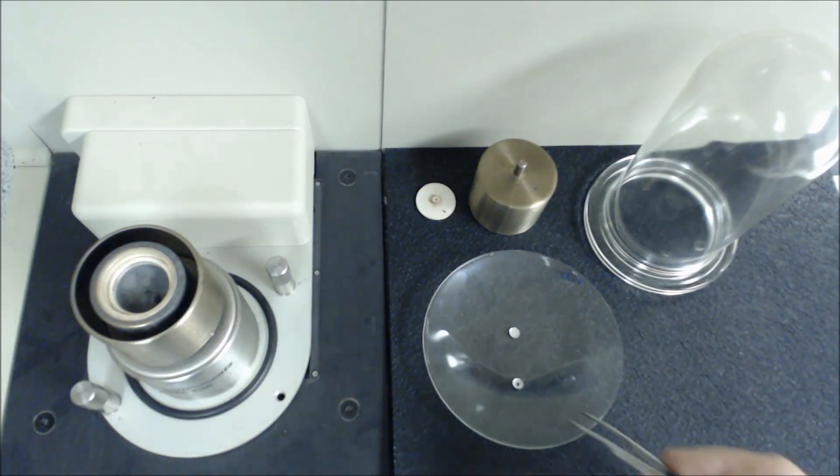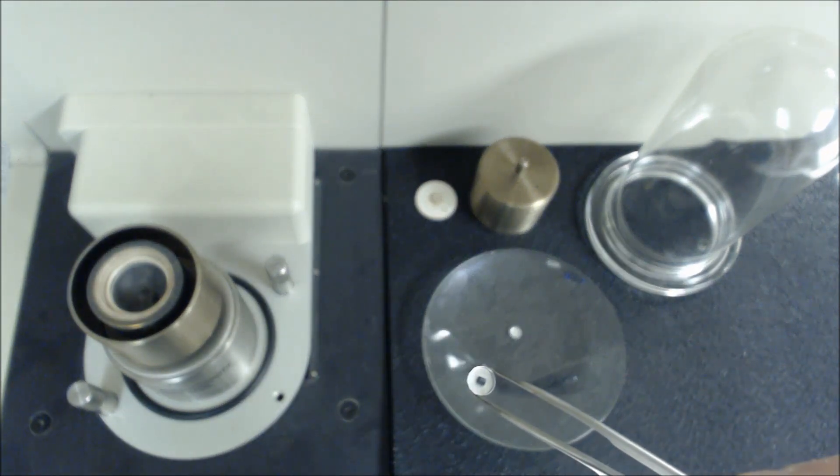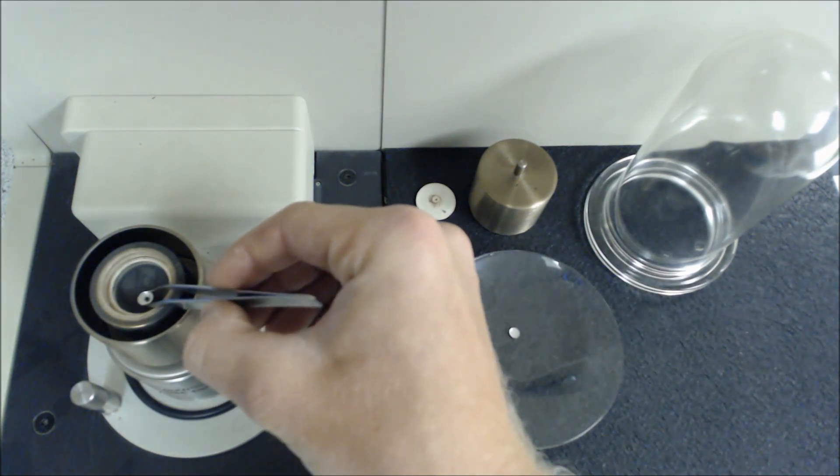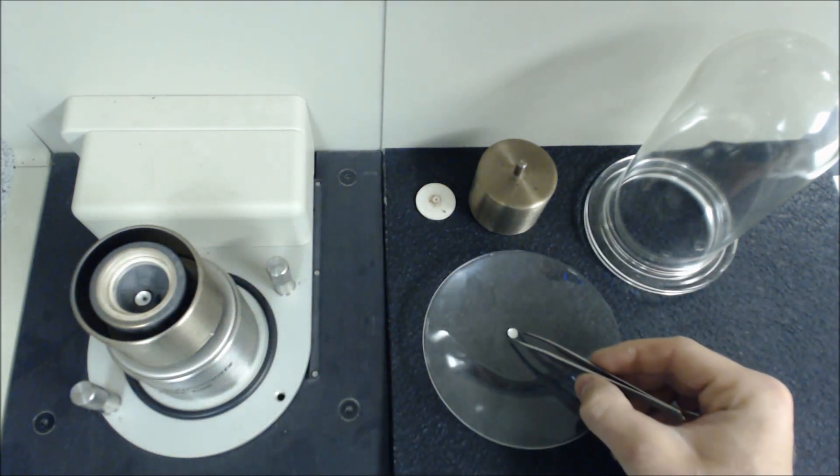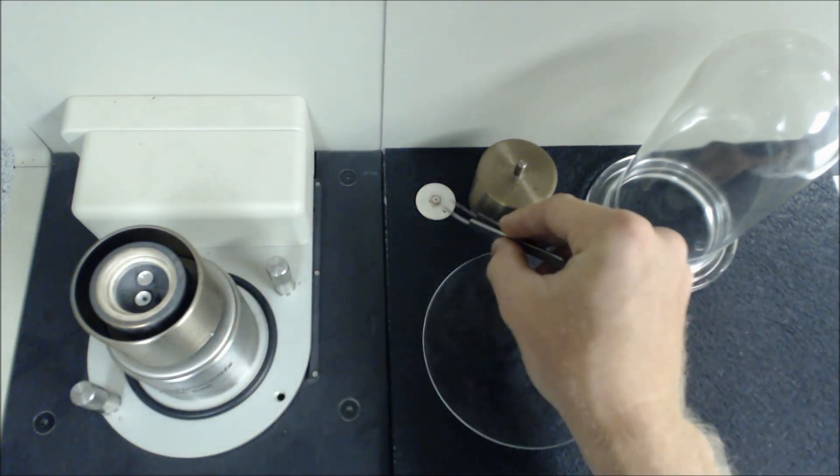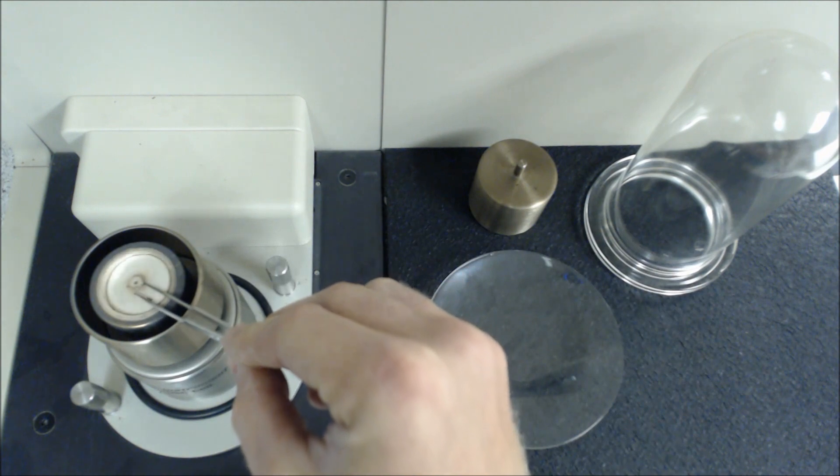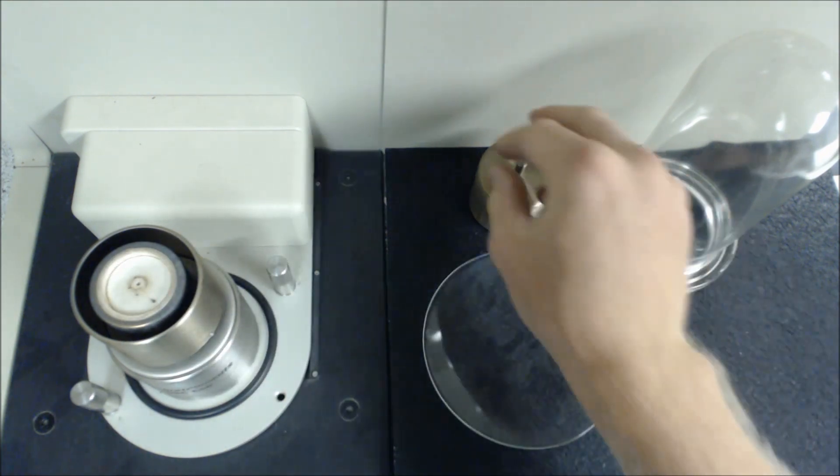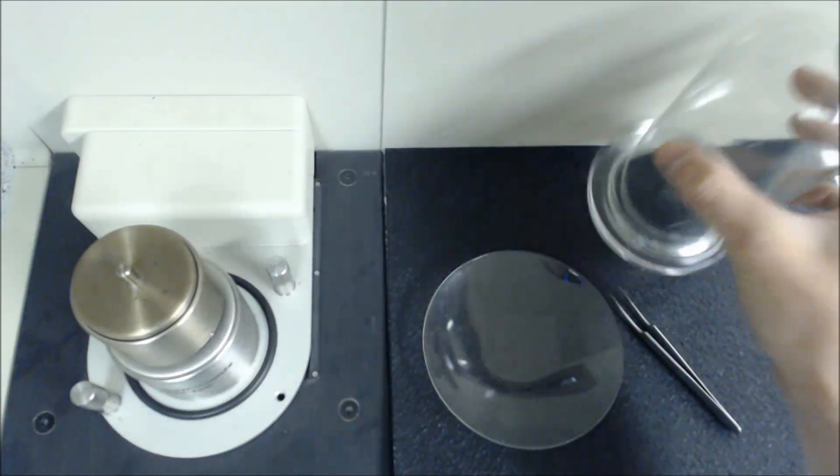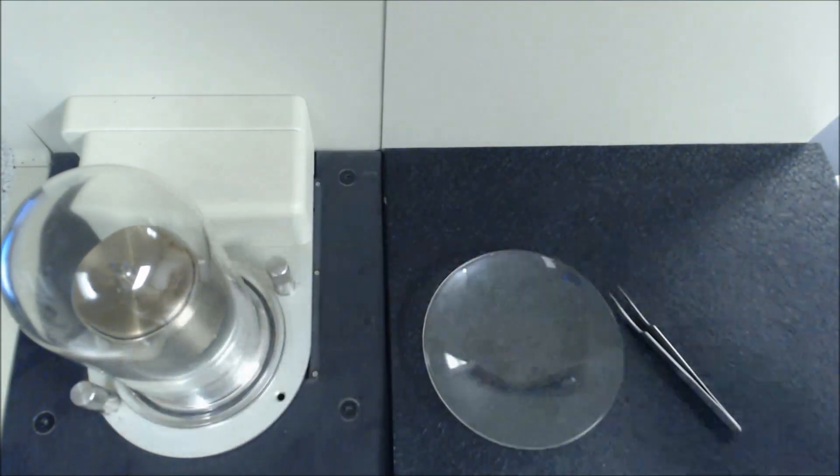To load the sample pan into the DSC, first we pick it up with a pair of tweezers and very carefully place our sample pan onto the front scale of the DSC cell. Then we take a reference pan which is of the same mass as the sample pan but empty and place that onto the rear scale. Then we take our thermal lid, place that on top. Now we're going to take the metal shield and place that on top of there. Now we take the glass dome which traps the gas within the DSC cell and place it on top making sure you have an airtight seal.